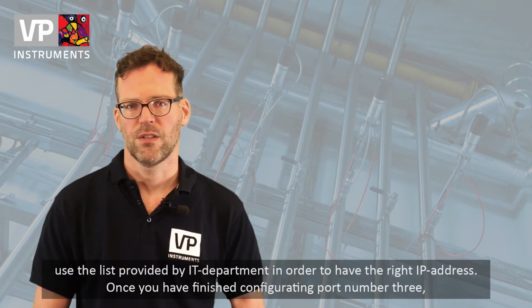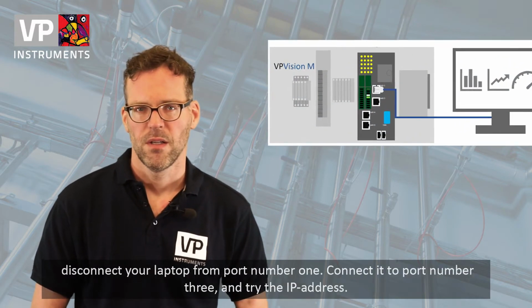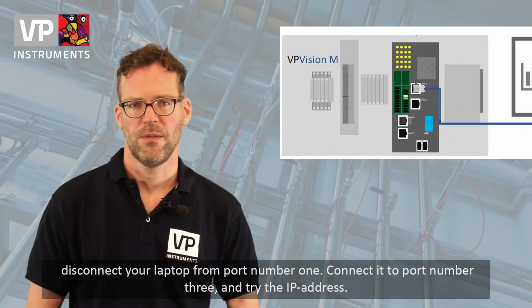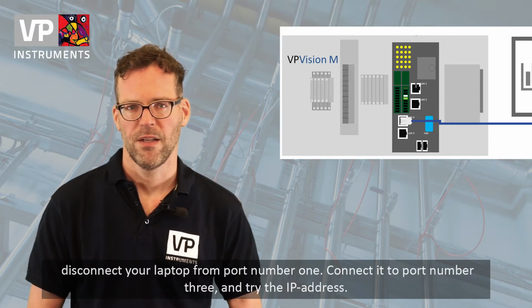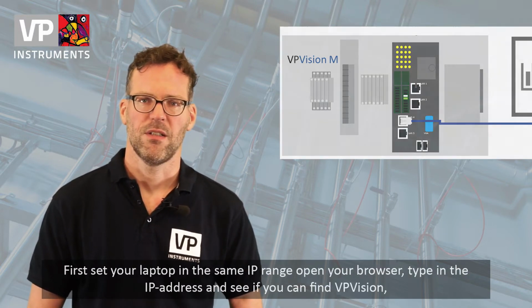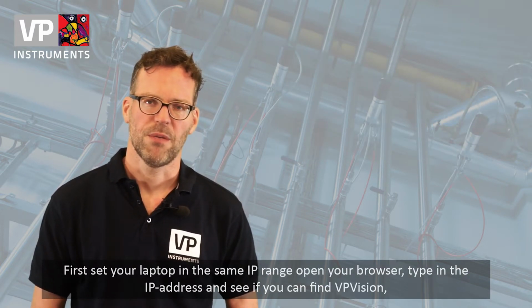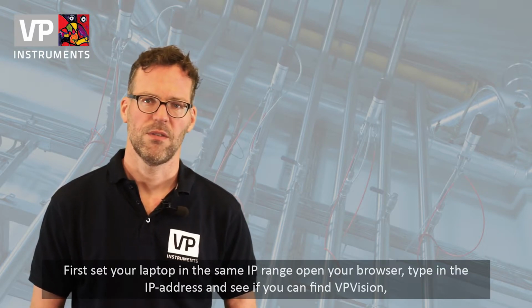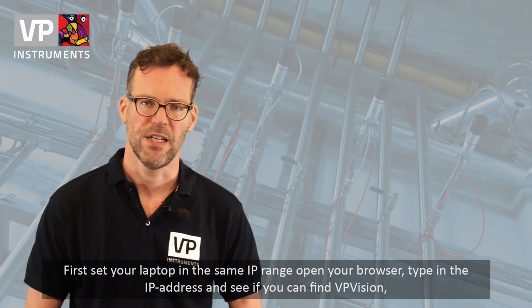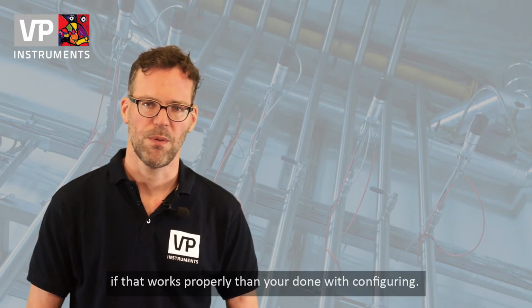Once you're finished with configuring port number 3, disconnect your laptop from port number 1, connect it to port number 3 and try the IP address. First set your laptop in the same IP range, open your browser, type in the IP address and see if you can find VPVision. If that works properly, then you're done with configuration.